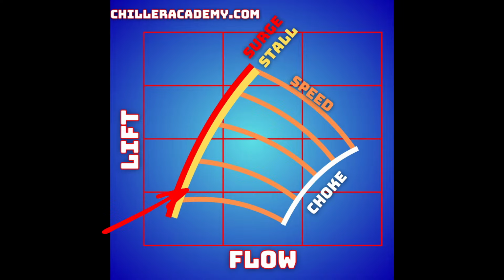This is what they would call it. So you've got low end surge, high end surge. High end surge, you've got a high load scenario, high lift, and you surge. Low end surge, you've got a low load, maybe lower lift, but yet you still push into a surge, right? When you hear those high end, low end surge terms, which are just kind of field talk in my opinion, I haven't seen literature that uses terms in that way, that's what's being described. So this is possible.